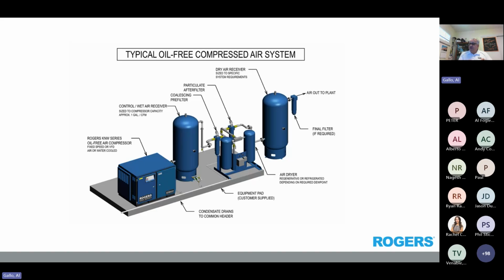So we could put that post filter in front, but a post filter works better when the dew point's a little lower. It's more efficient. So it's pulling out more of any hydrocarbons and anything that may have kind of slipped through the refrigerated air dryer. But on a desiccant dryer, we do just the opposite. We put the high efficiency first because we don't want to contaminate the desiccant. So coming out of a compressor, being an oil lubricated or an oil free for that matter, keep in mind that oil free is still ingesting air out of the atmosphere that you and I are breathing right now, which could have hydrocarbons, could have organic material, could have whatever. You could have hair and dust and skin cells and all that sort of stuff.